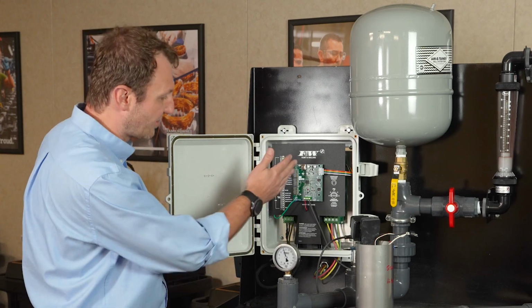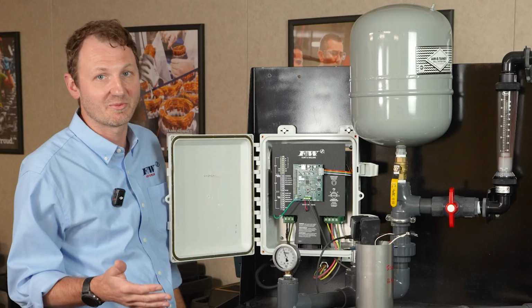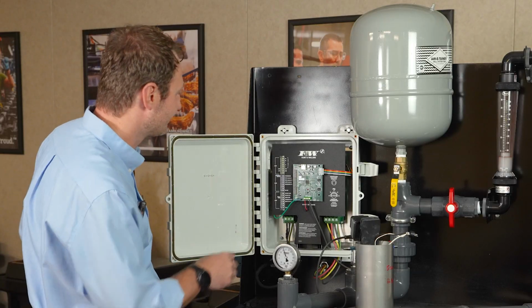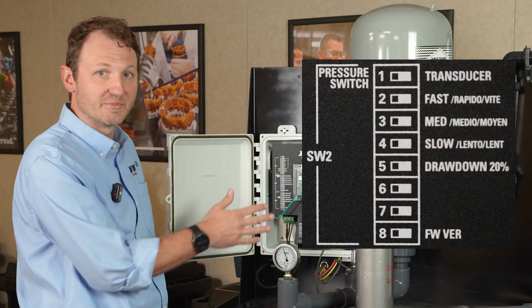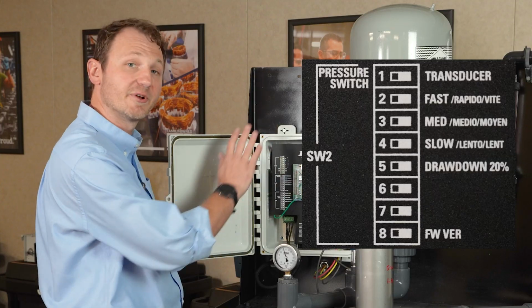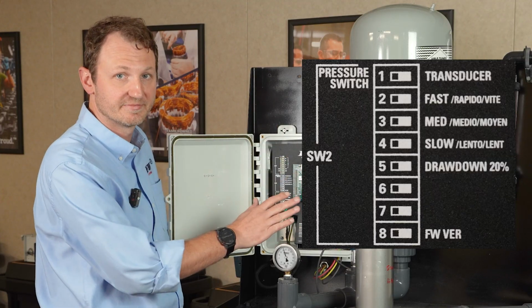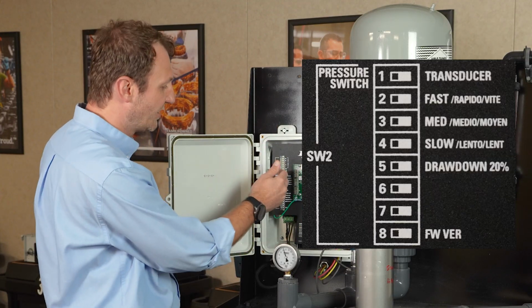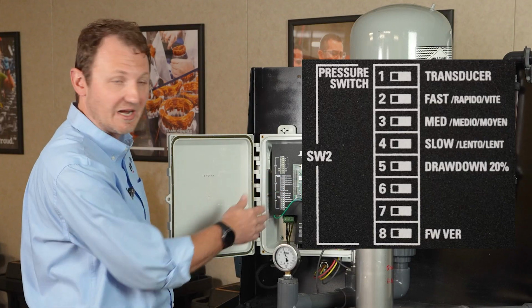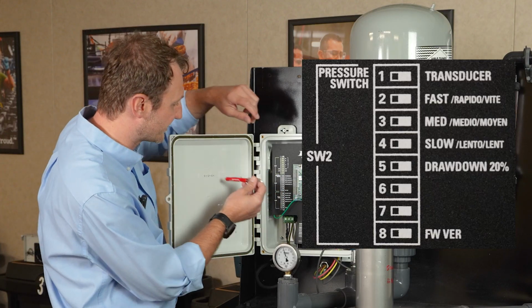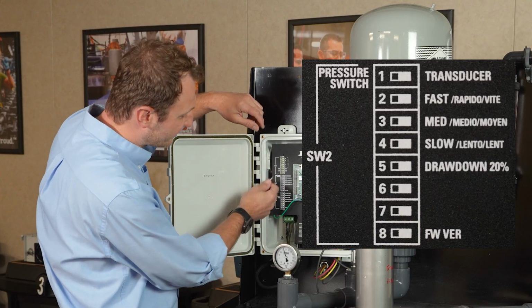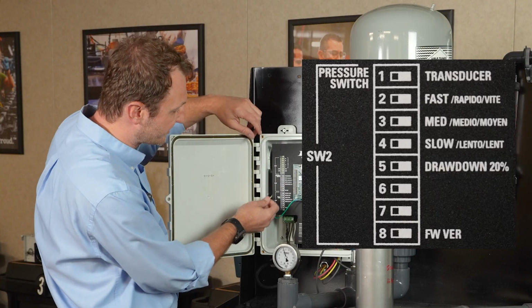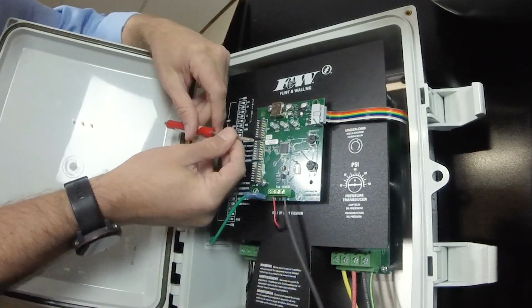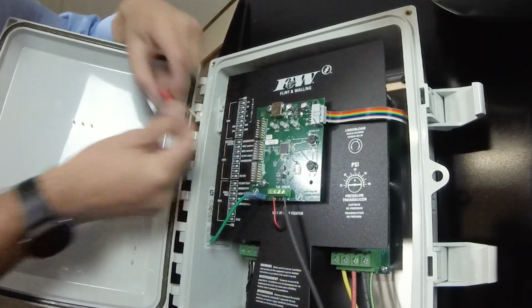8 is not used. So dip switch bank number 1, we just want to make sure we've got the 1.5 horse turned on. Moving down to bank number 2. Bank number 2 is everything having to do with your pressure. Okay, so if you think of it, motor, pressure, and additional options here in bank 3 we'll get to in just a minute. So option number 1 here is pressure switch or pressure transducer. I've got a transducer here, so I'm going to turn on number 1 for transducer.